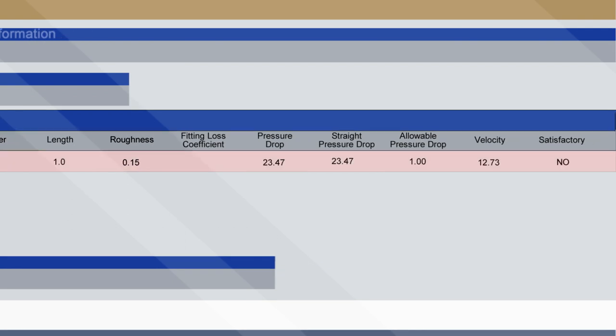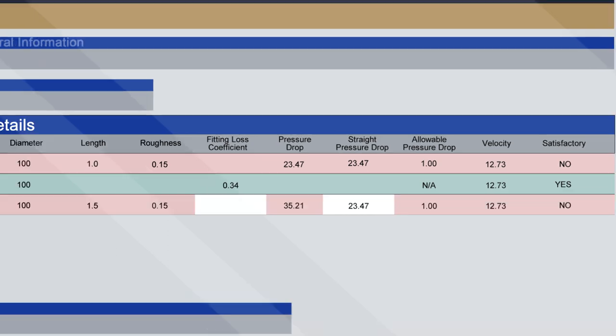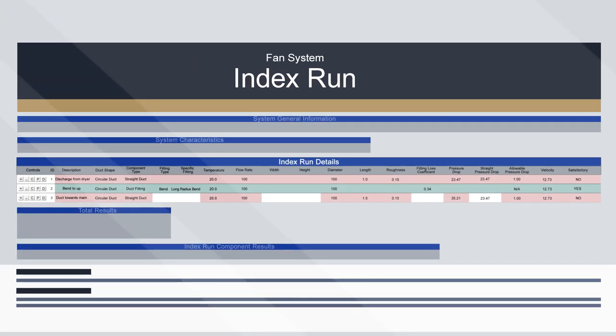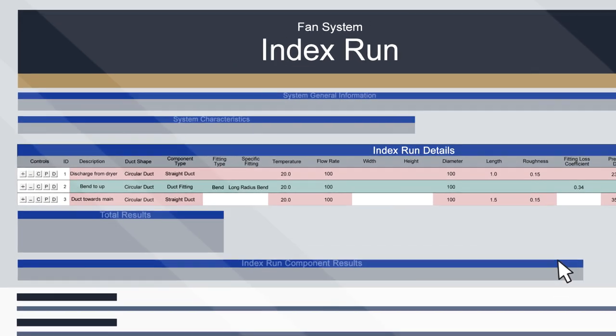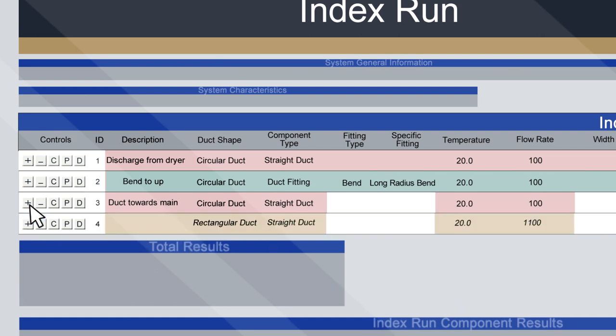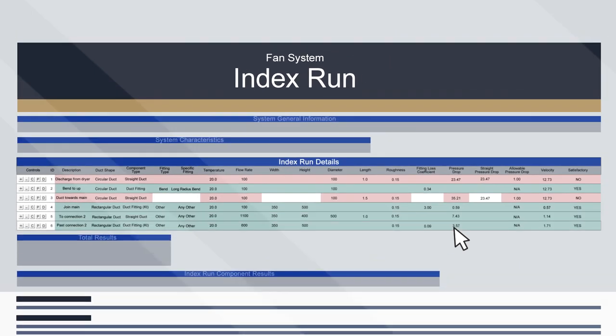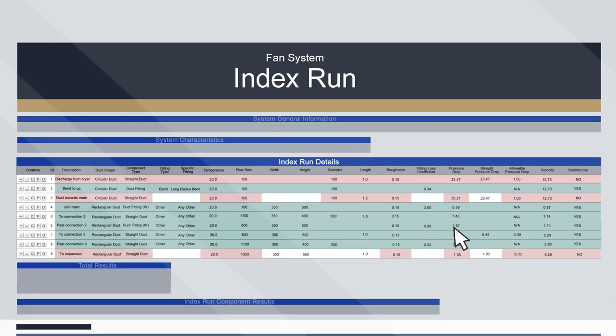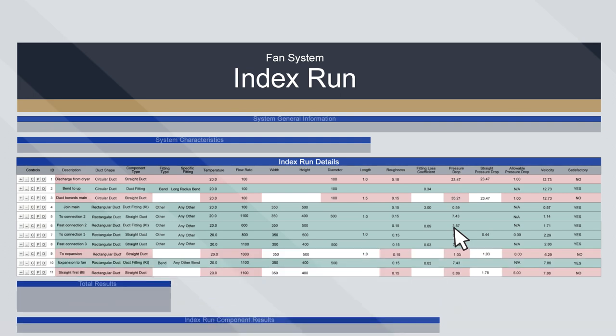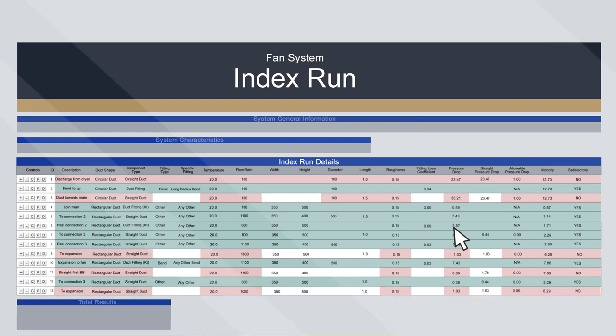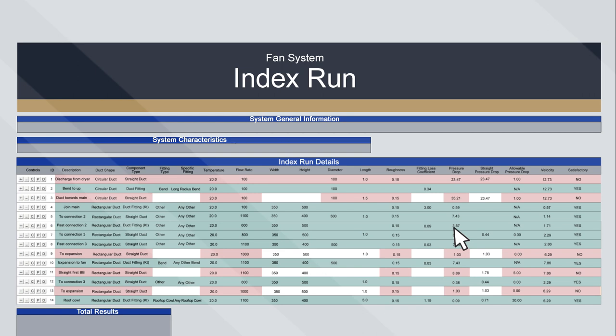The results for each row are automatically calculated. Red indicates a component which doesn't satisfy the Clause J5.4 requirements, while green indicates one that does. However, a component showing as red may still form part of a compliant system. In this example, the next component is a fitting, so the component type needs to change accordingly, along with other parameters. Continue to add rows, amending the default parameters or copying and pasting information as you go, so each individual component — whether straight ducting or a fitting — needs to be entered to model the entire system. This is how the complete duct system for this example looks.